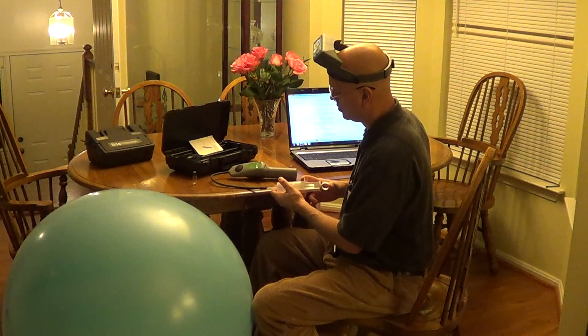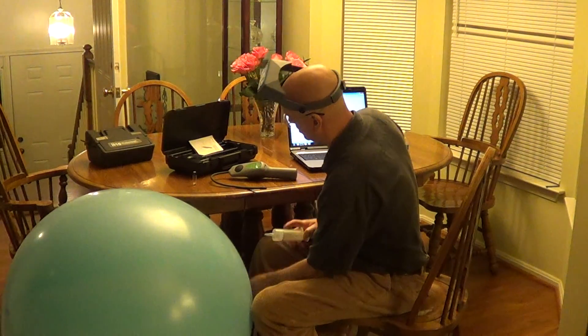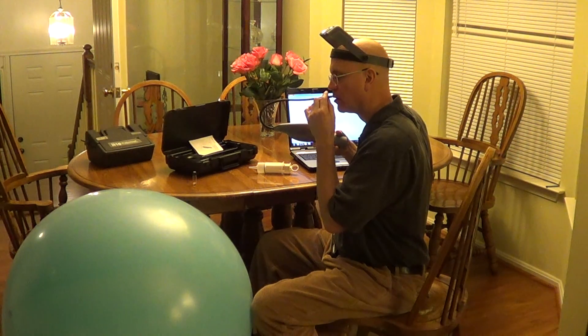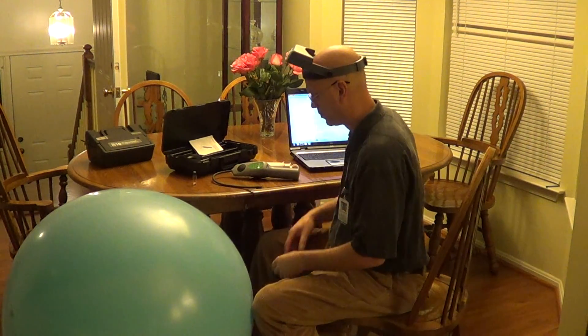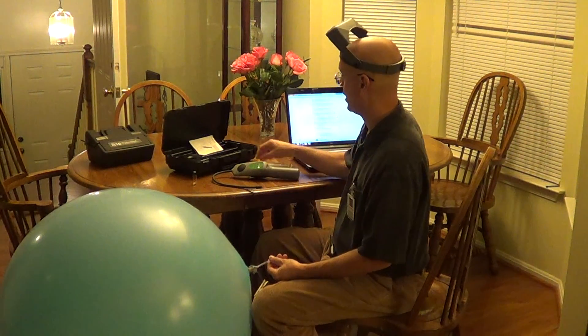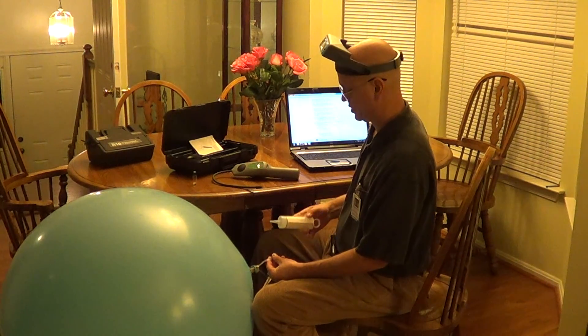It's less than a second response time. I'm going to count it — before I even finish, it's already setting it off at one part per million. It's because it's got a pretty decent suction on it. I can't really feel the suction, but the sensor is located right here. It looks like it just draws a vacuum in that whole area. It's got to have the rubber cap in place. One part per million again — sets it off.